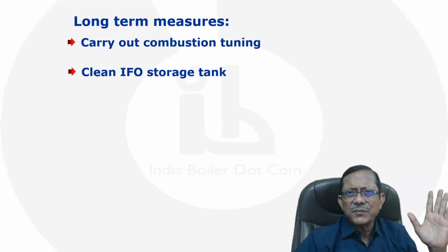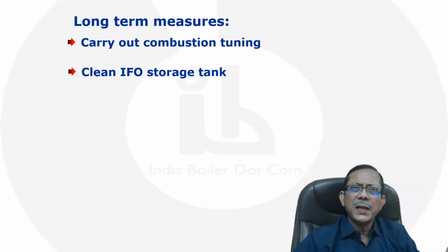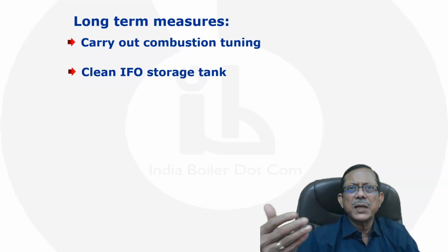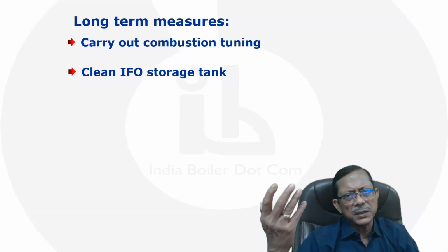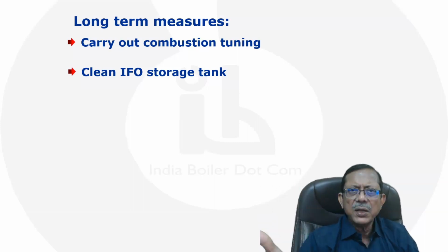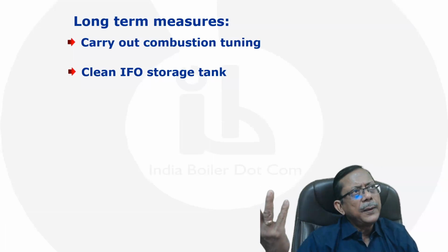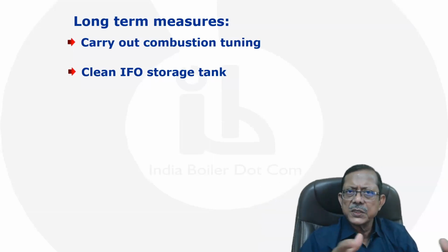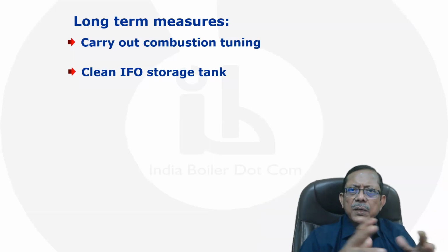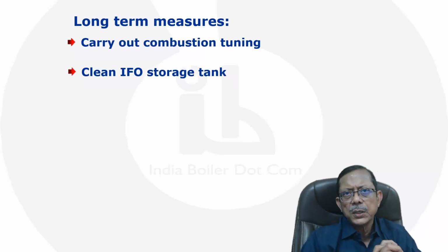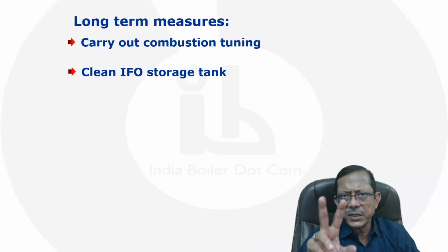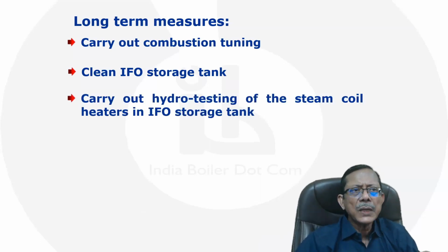The storage tank, which they have not cleaned since commissioning, and a lot of sludge is getting accumulated. It is a big job, so that's why it's a long-term measure. But at one point of time they will have to do it, right? In fact, 3-4 months after this assignment was over, I got the feedback that yes, they have gone for cleaning of one of the storage tanks, because they had 2 tanks.